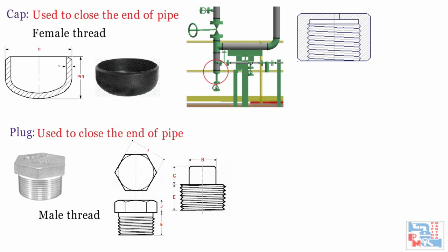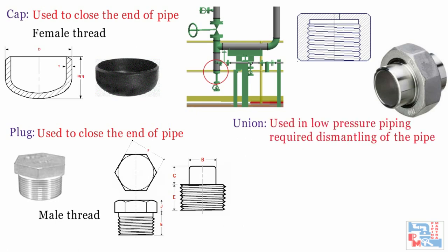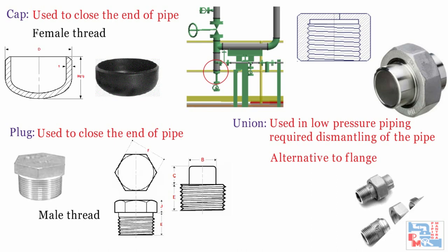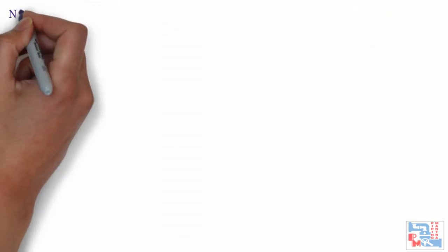Unions are used in low-pressure piping where dismantling of the pipe is required frequently. They are used as an alternative to flanges. A union can have threaded or socket welded ends. There are three pieces in a union: two end pieces attached to the run pipe, and a third threaded piece to connect these two. A metal-to-metal seating ensures sealing.